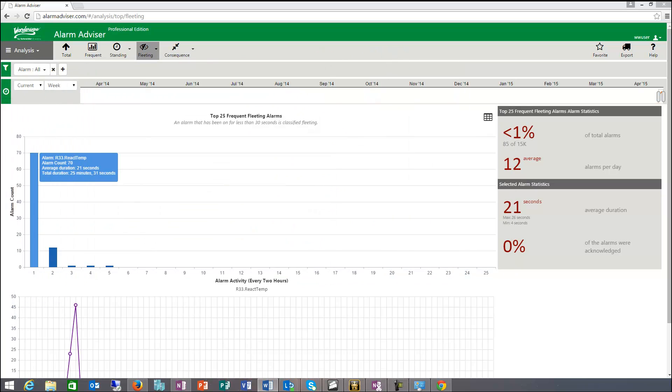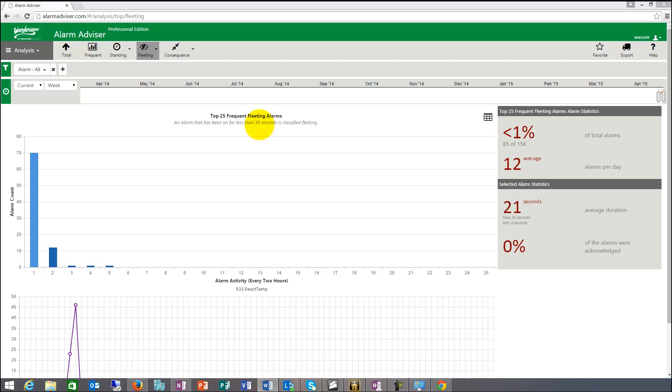Criteria can be set around alarm duration, chatter time. So things, they're also sometimes called chattering alarms. Things to do to get rid of these is more put bounce and debounce timers into the system. A certain amount of time, like here, I'm looking for, I think fleeting is defined as 30 seconds in the system. I can put it to 15 seconds or 10 seconds. And then basically anything that comes and goes within 10 seconds is identified as a fleeting alarm.